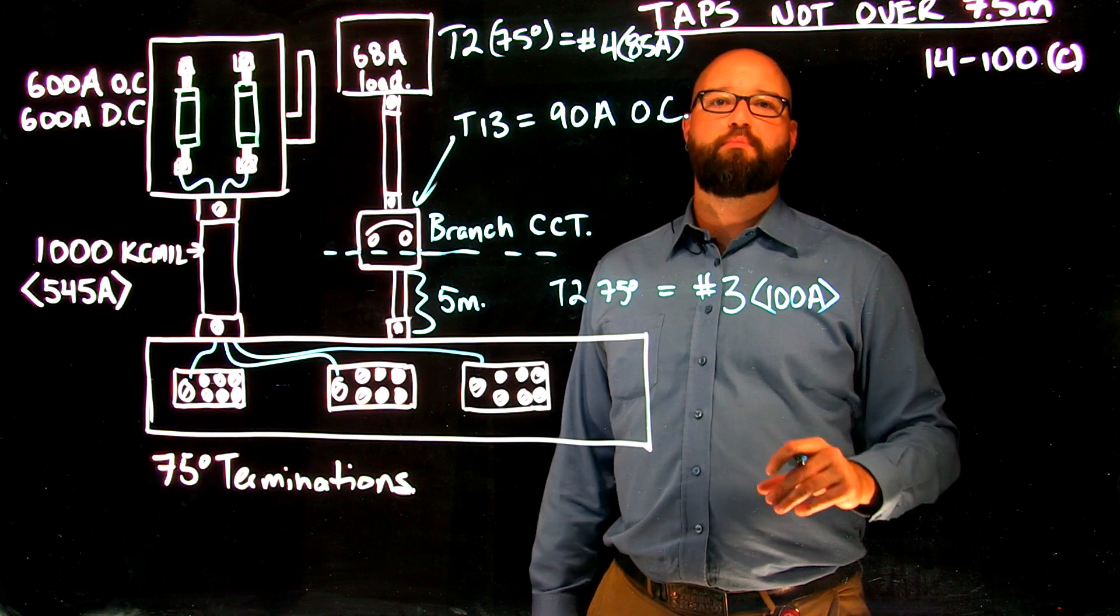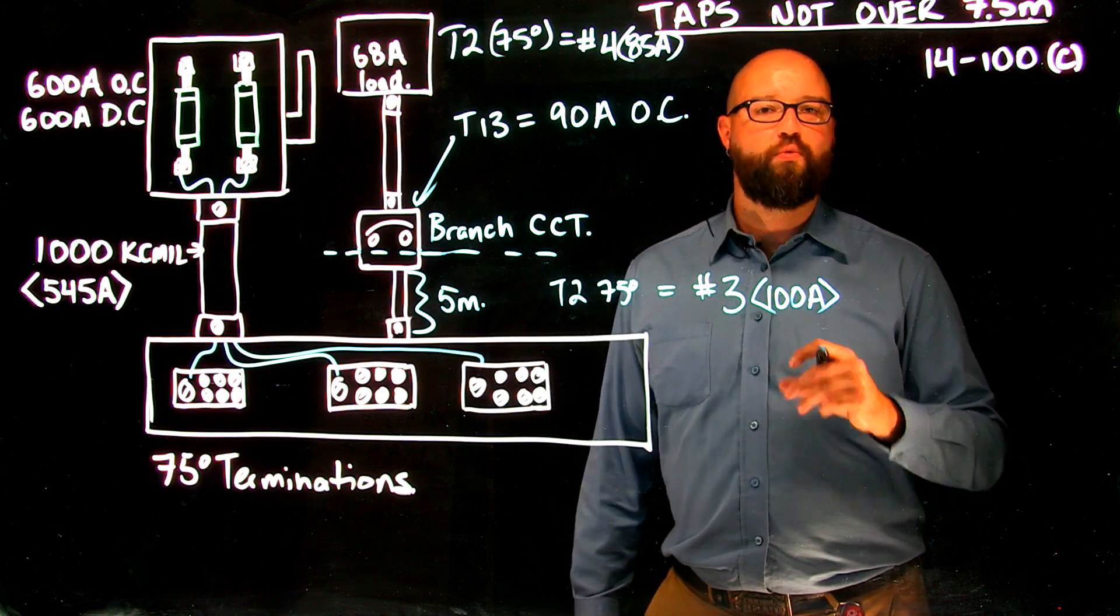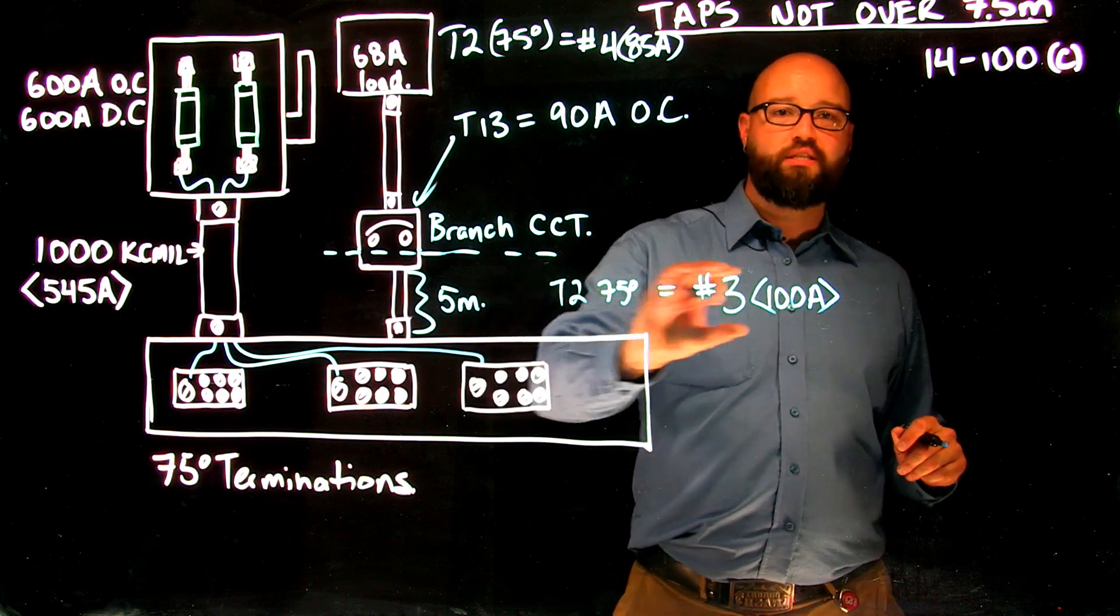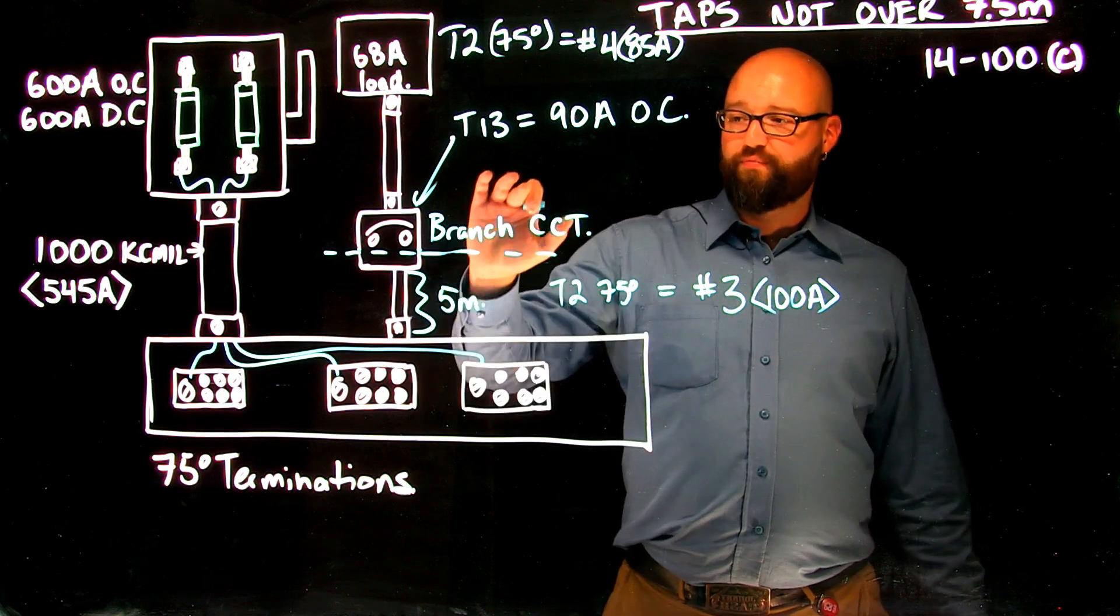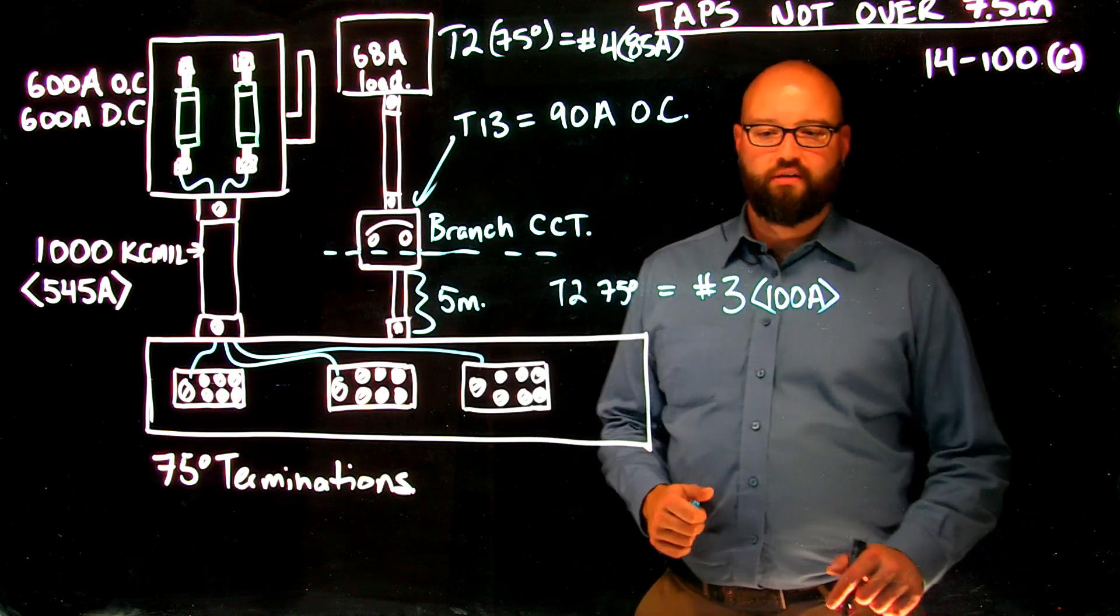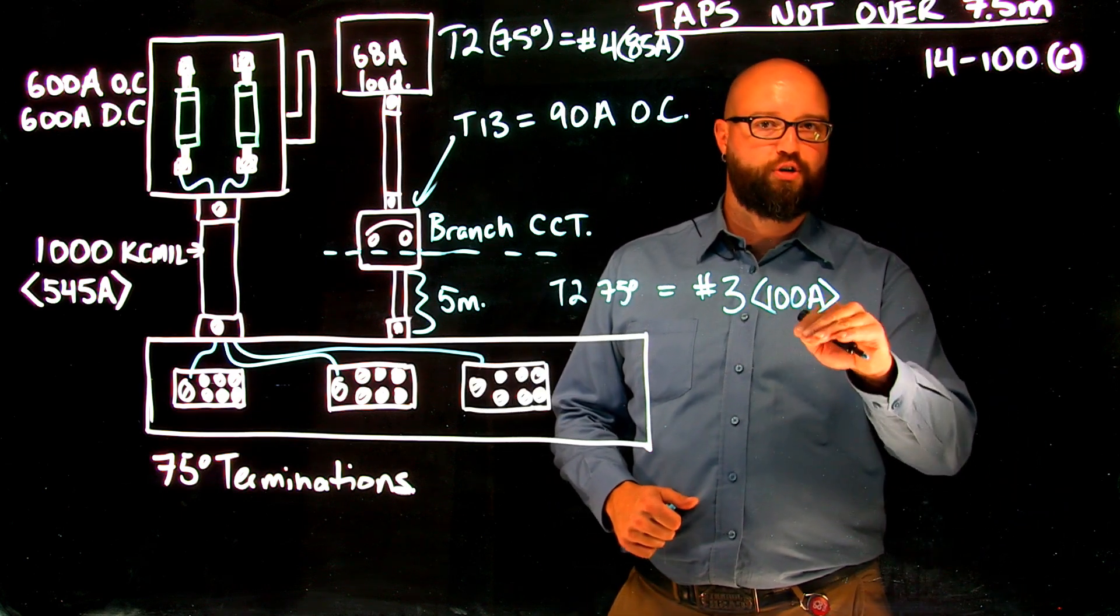Now this is not a choice that you get to make. It is the larger of the two wins in this situation. So what we need to do first is figure out what is the tap conductor based off the overcurrent that it supplies. It needs to be larger than that. That's our first. So we end up with the number 3 as the first portion of our choice.